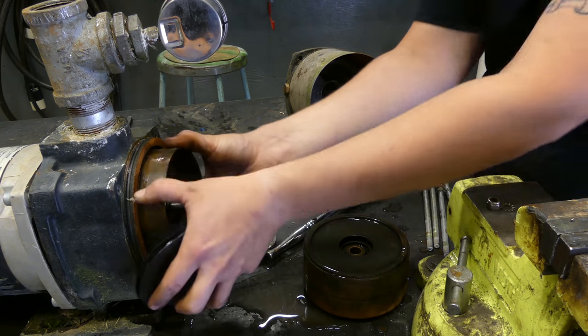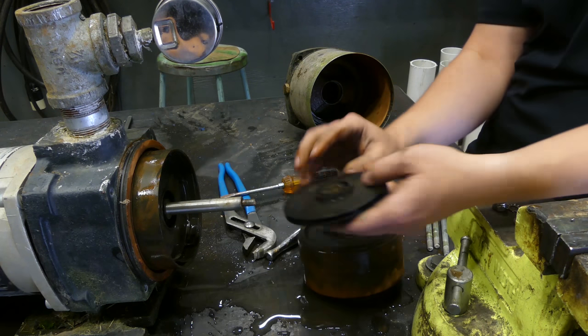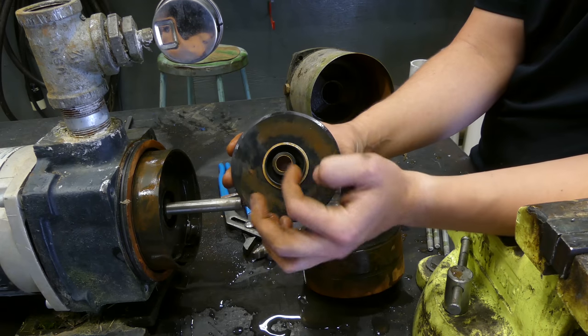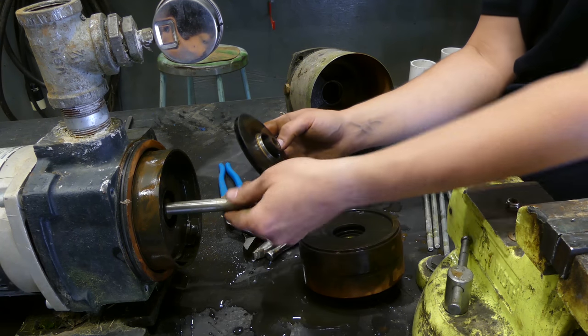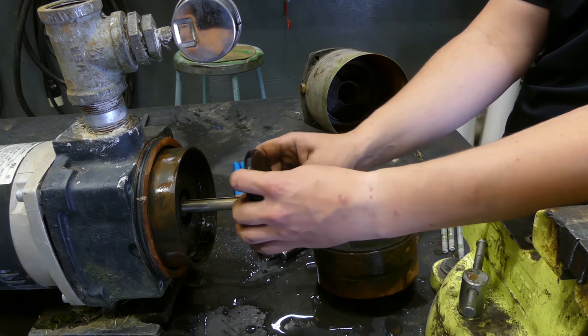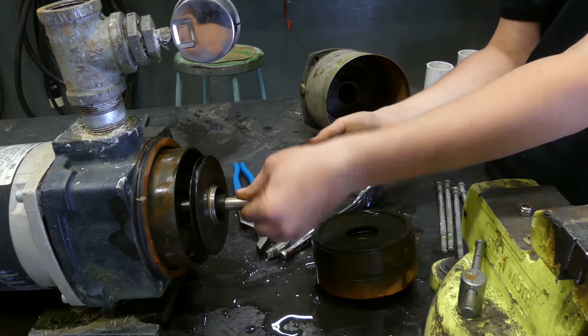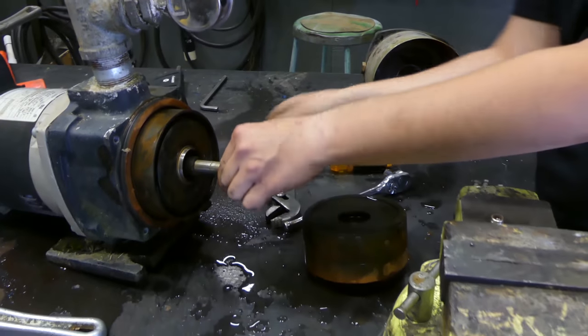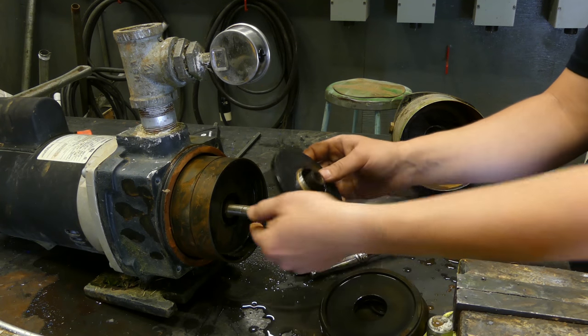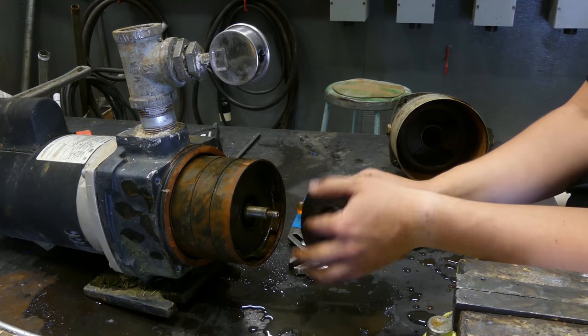Not a tremendous amount of wear — that looks pretty good. These aren't actually supposed to rotate, so that's not critical. Just the impeller rotates. That impeller looks good to me. There's a little doohickey on the inside — it goes on the underside of the shaft in a channel, so that when the shaft rotates, so does the impeller. That looks fine — no issue. Last but not least, that one looks fine too.